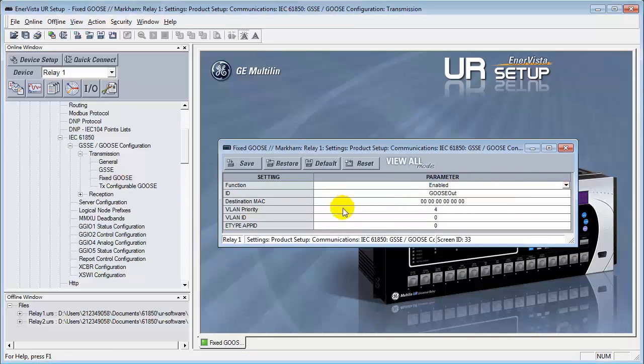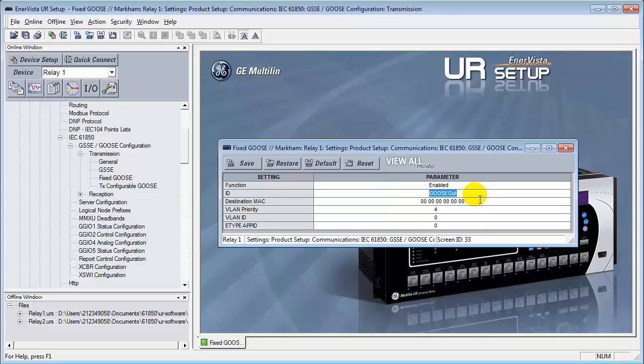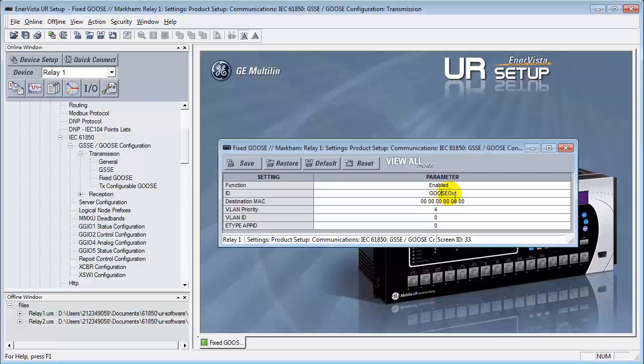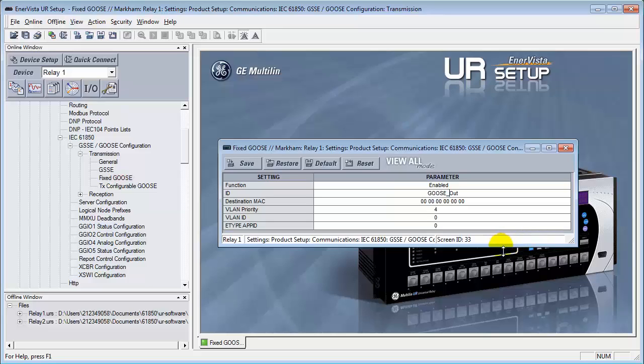We'll enable it to begin. And the ID is the name of the goose message itself. Every goose message that's going out across the network has to have a unique name. There are some naming criterias that we have to be aware of. We cannot leave any spaces between two words unless there's an underscore between the two words. So to have a word, a goose message name like this is totally illegal unless it's covered by an underscore. So in this case, we're going to call this goose message motor_A.